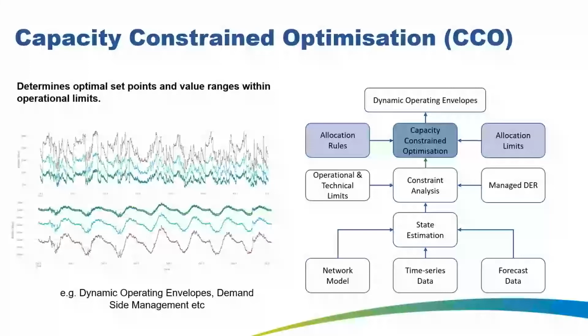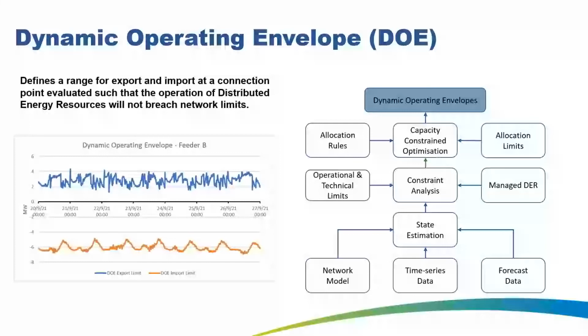Then we lead to the generation of these dynamic operating envelopes. That's really, as Peter described, this range of operation, so that at the connection point it describes export and import limits. The DER operating behind the meter is considered along with load or self-consumption on site and generation at that time, so that overall the customer site stays within the export and import limits of this envelope.